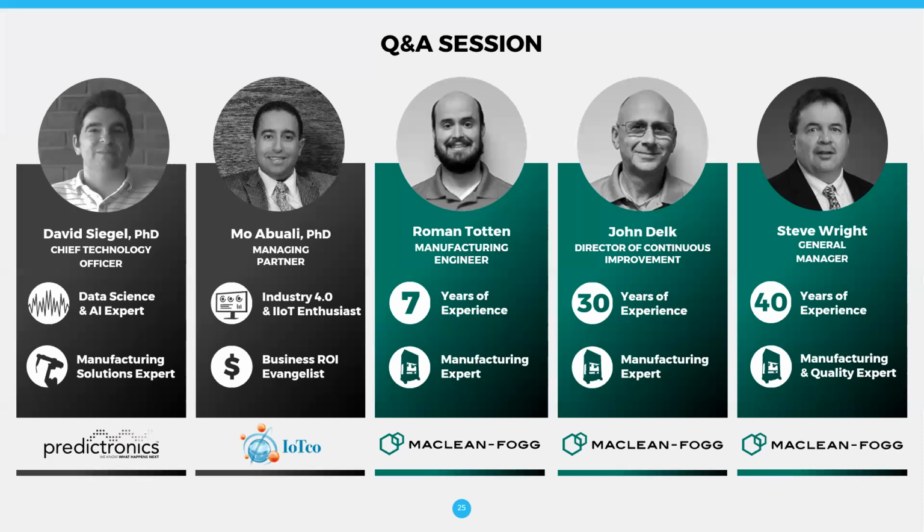Yeah, that's correct. Once again, we're pulling multiple data. I'm looking at it daily. And Predictronics does a good job of showing a number of features. I think I saw a question in there about how many features we are gathering. I alluded to some of them between motor amp draw and tonnage and bar temperature, but just for the vibration sensors themselves, I want to say we're gathering probably about 400, 500 different features, but not all of them are feeding directly into the health plot.